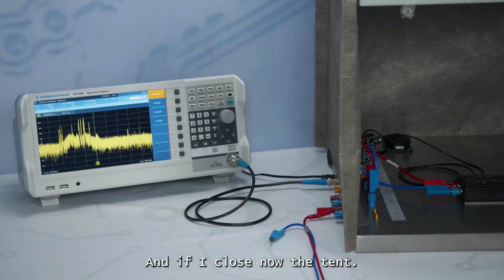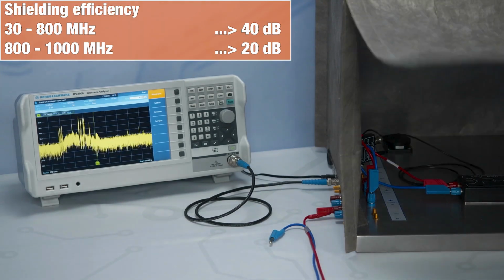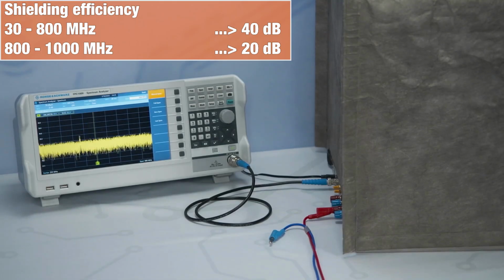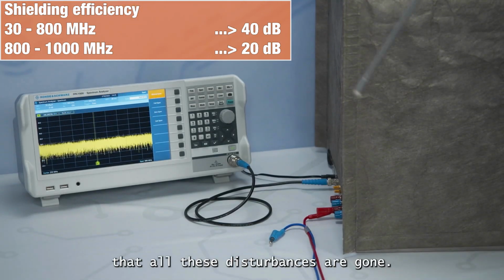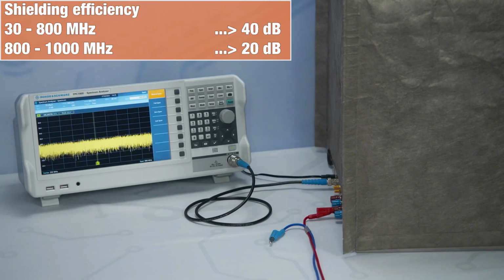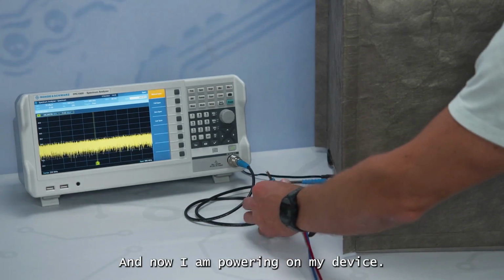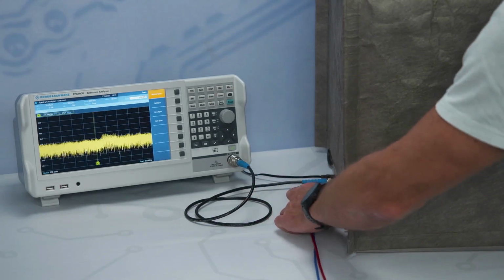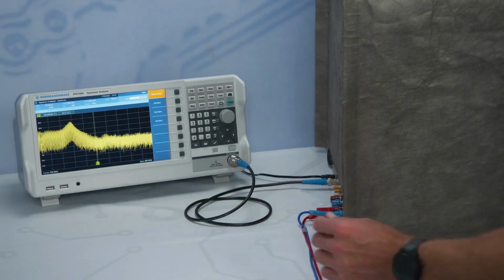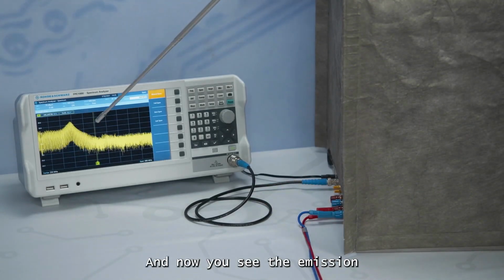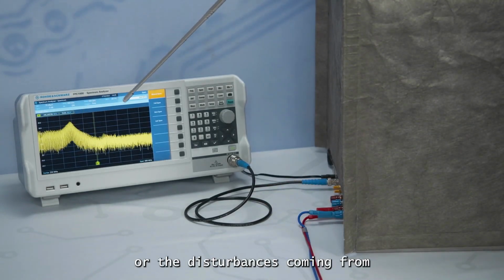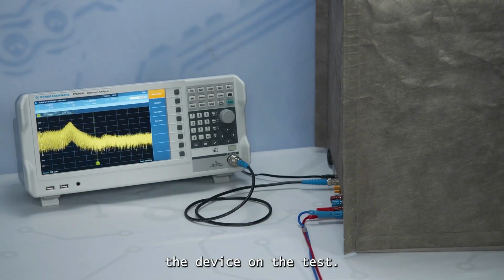And if I close the tent now, then you see that all these disturbances are gone. And now I power on my device, and now you see the emission or the disturbances coming from the device under test.